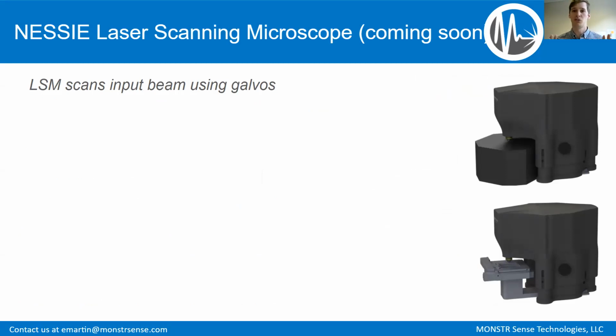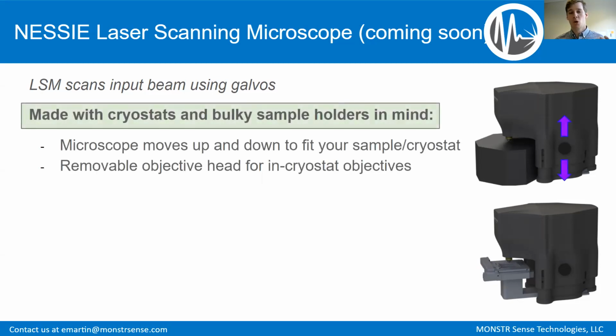A laser scanning microscope uses 2 galvos to rapidly scan the beam over a sample. We were looking at laser scanning microscopes on the market and didn't find one that really fit with what we wanted to do. So we ended up here at MONSTR Sense building our own. One thing we were particularly interested in is that we wanted to be able to work with cryostats and bulky sample holders. Conventional microscopes made for biologists with their slides really didn't cut it, because some people want to work with samples that are heated or, again, in cryostats.